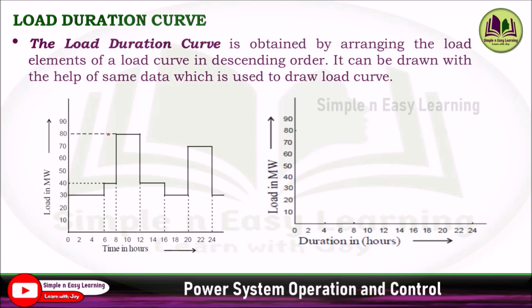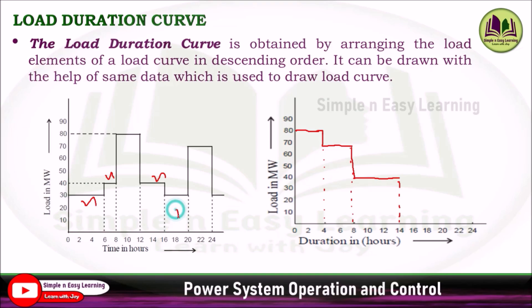Here we can see that 80 megawatt is the maximum load, lying between 8 AM to 12 noon — that is, 4 hours. So the maximum demand of 80 megawatt lasts for 4 hours. The next maximum is 70 megawatt, which also lasts for 4 hours, so it steps down for the next 4 hours at 70 megawatt. Then 40 megawatt: it appears from 6 to 8 AM (2 hours) and from 12 to 4 PM (4 hours), totaling 6 hours.